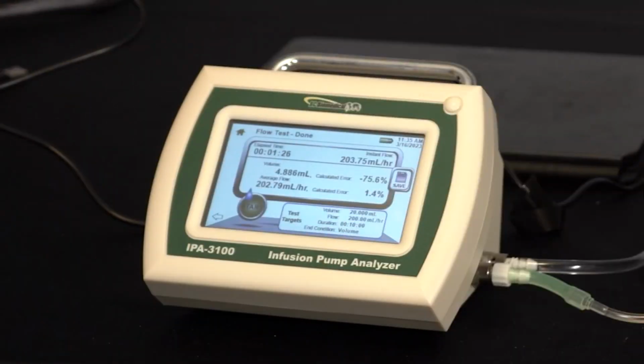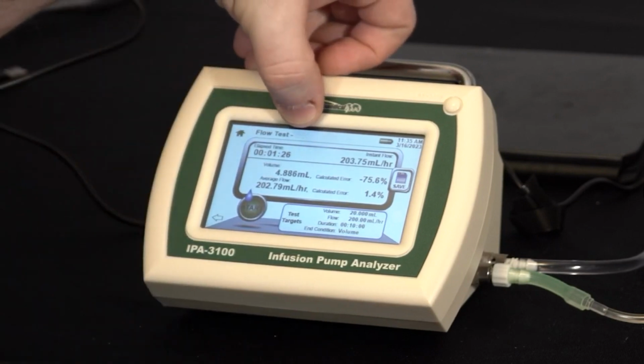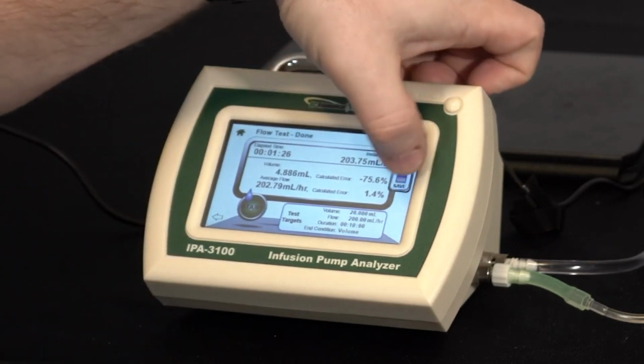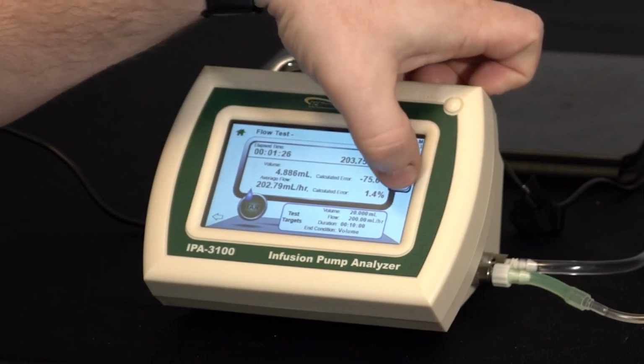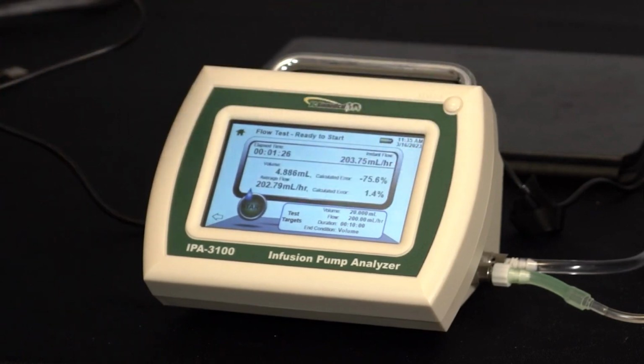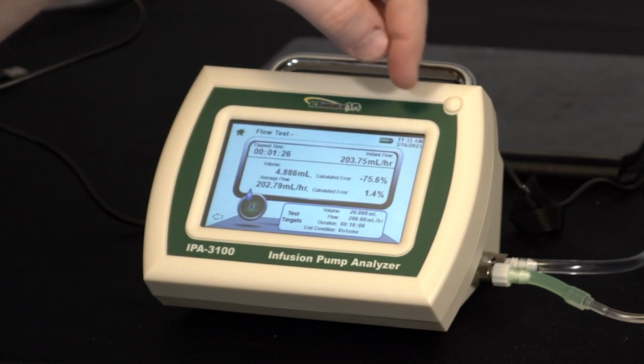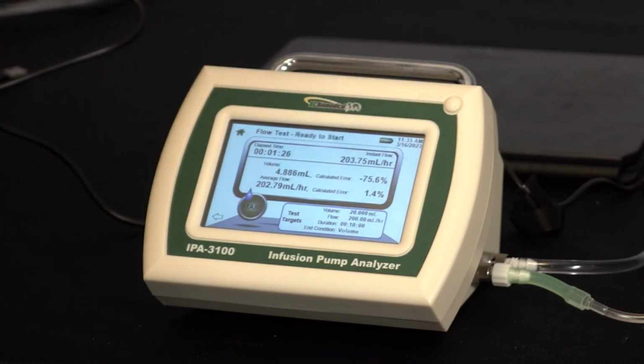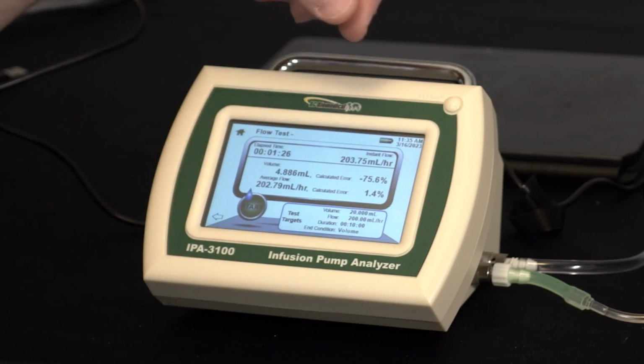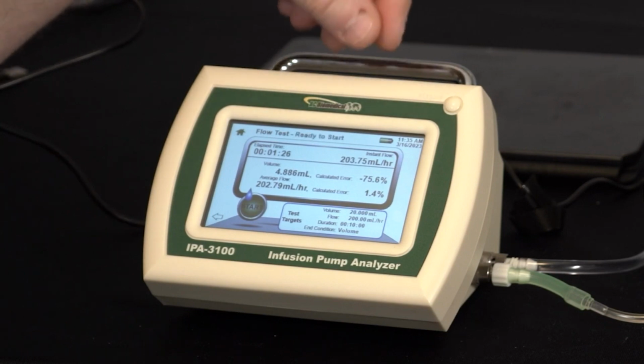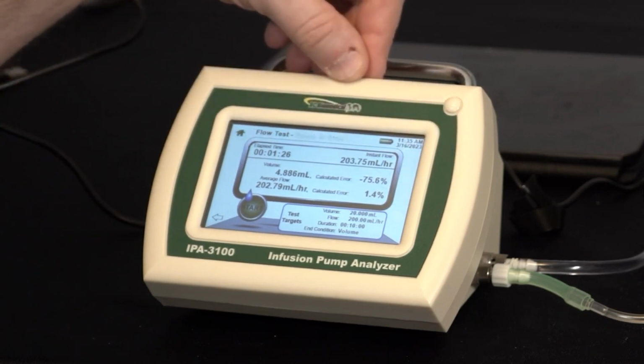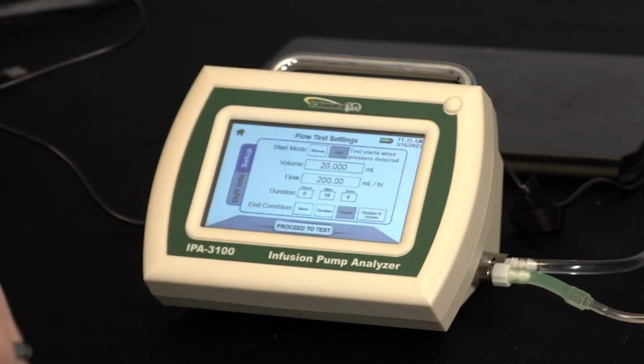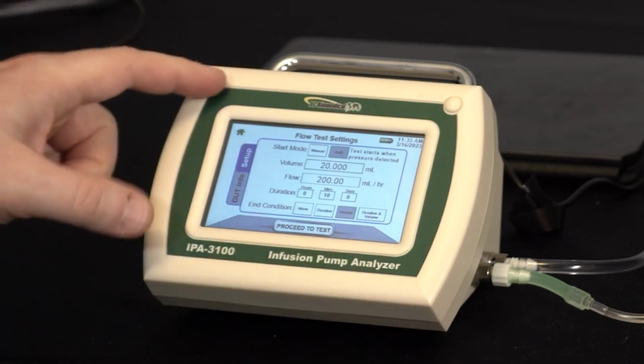So now at the top of the screen, we can see that the test is complete. It says done. We can save this record to our data log by pressing the save function here. And I'll show you another setting later on in another video. We'll show how to do autosave so that I don't have to worry about remembering to press that button at the end of the test. But if I don't want to save every single test that I do, I only want to save select records. This shows the manual save. That's been saved. I can go back and run another test. I can change my configuration and run a different flow rate or a different volume and continue on with that.